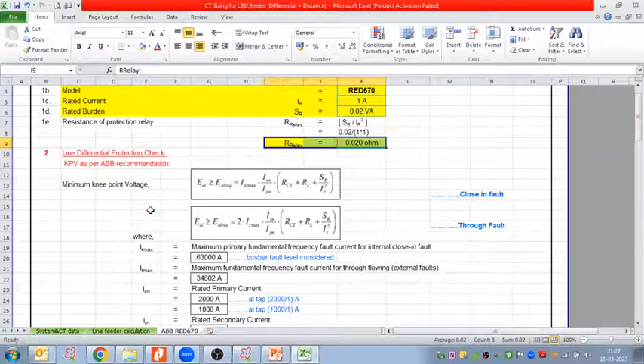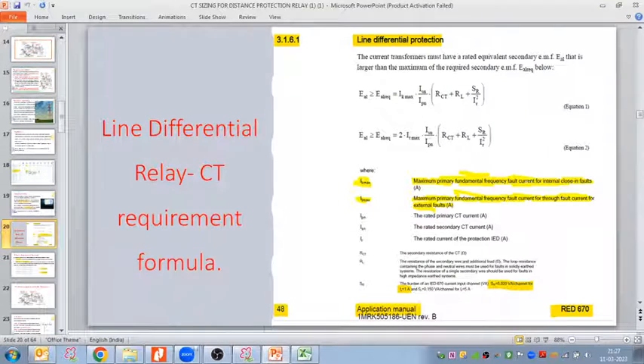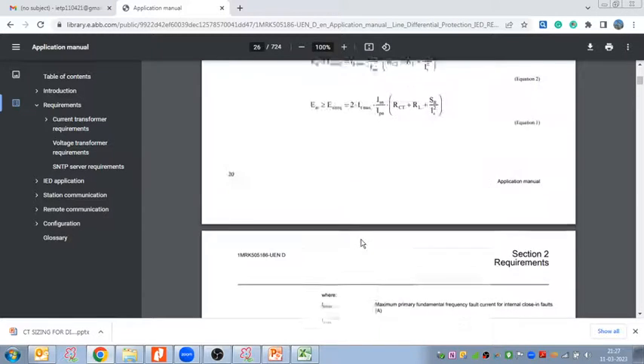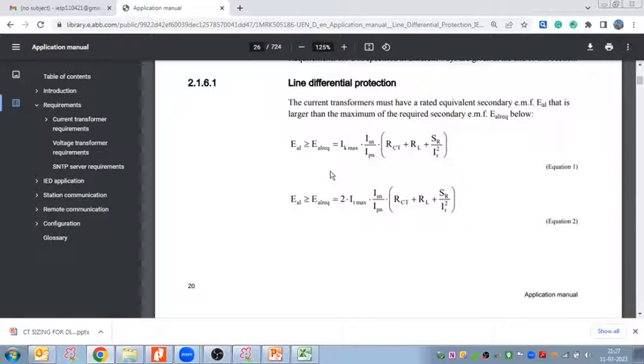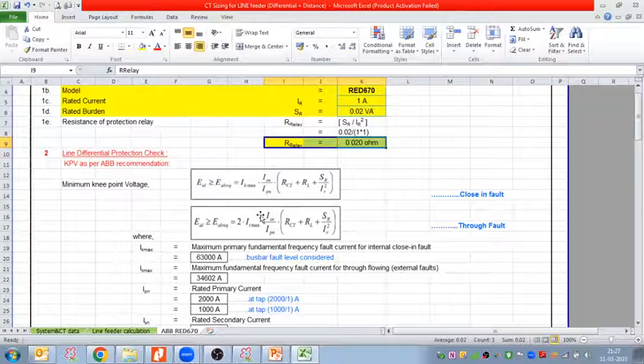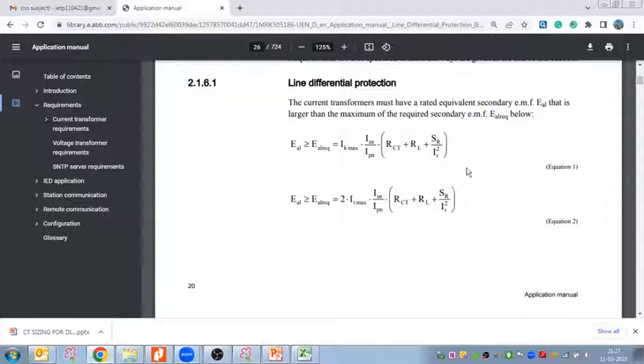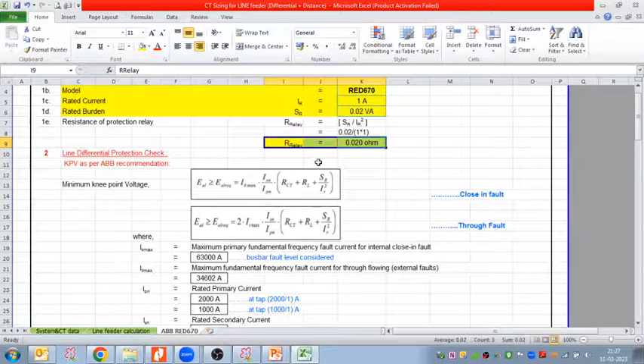Now, when I calculate the CT knee point voltage for the line differential protection, the knee point voltage, as per the ABB recommendations, the minimum knee point voltage would be given by this formula. This formula I took from here. So Ek should be greater than Ek required, based on IK max. This is the same extract I took and put here. Equation 1 is for the close-in fault, and equation 2 is for the through fault.